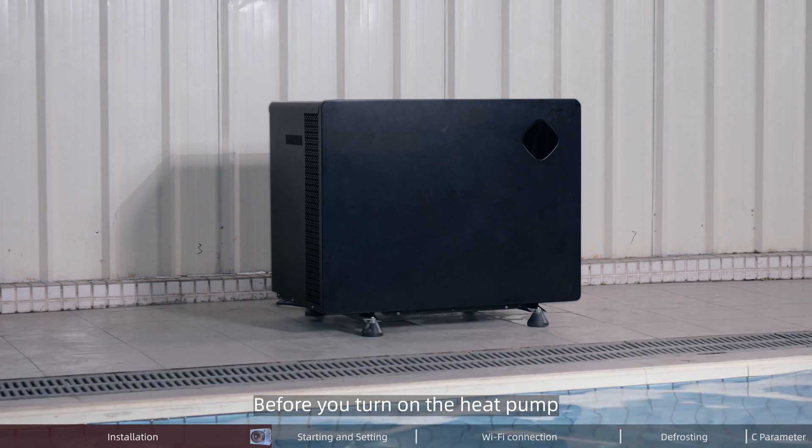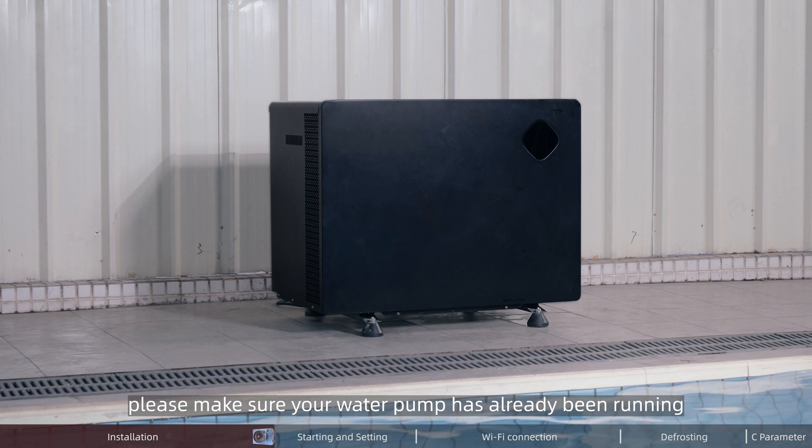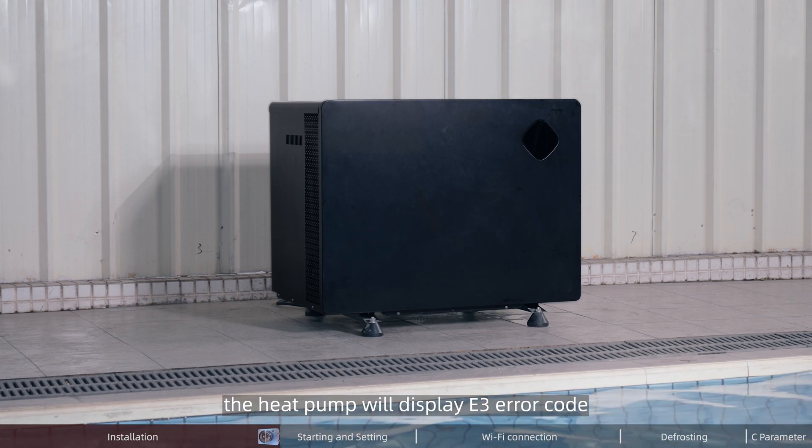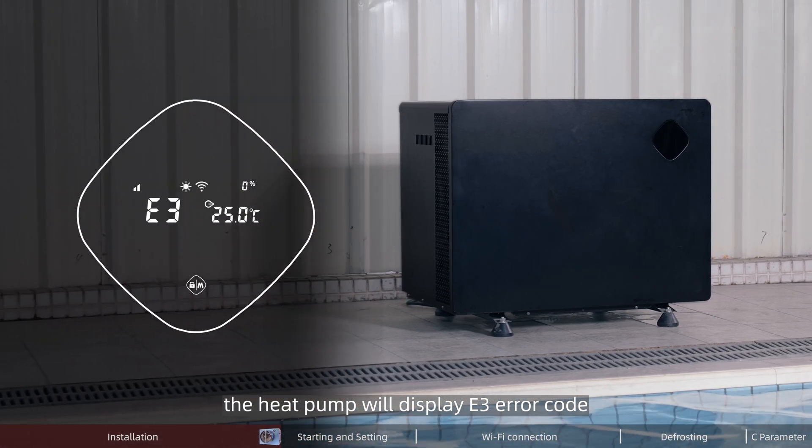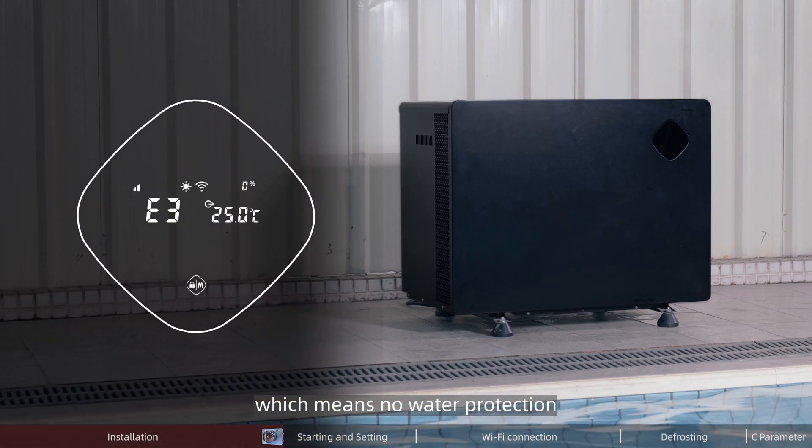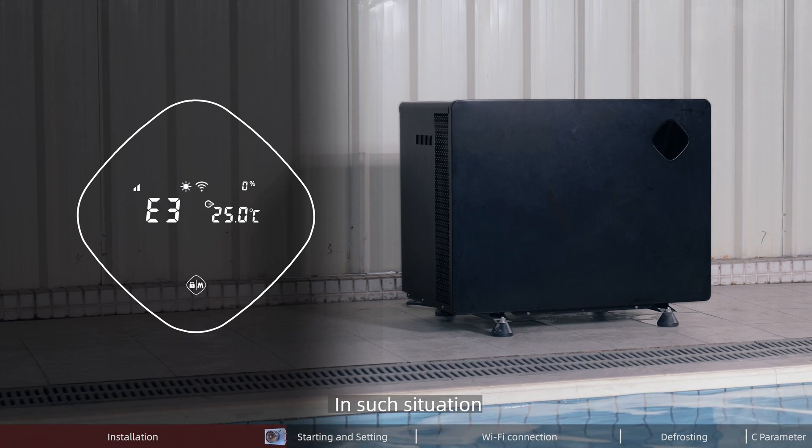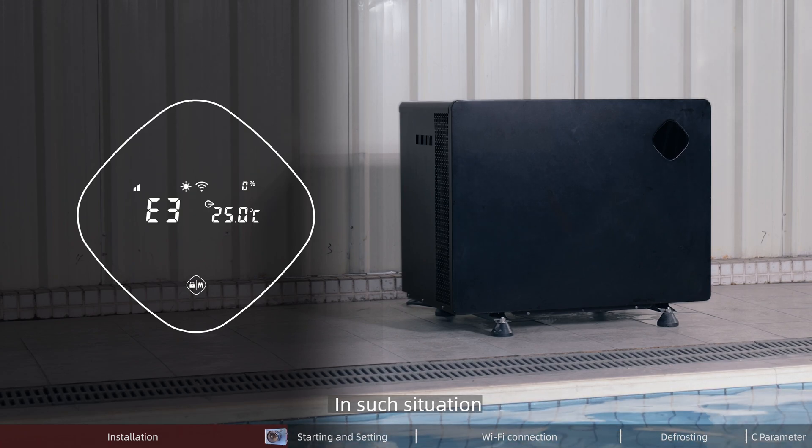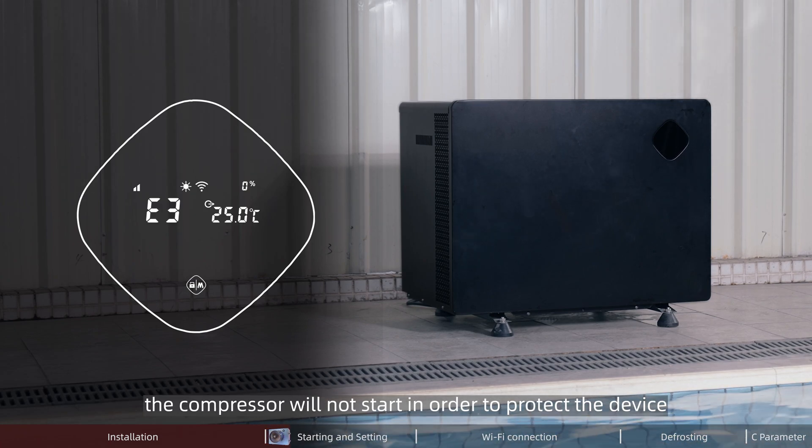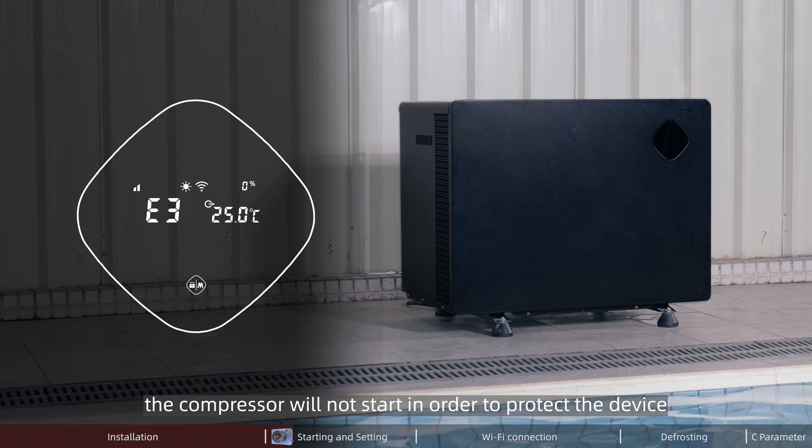Before you turn on the heat pump, please make sure your water pump has already been running. Otherwise, the heat pump will display E3 error code, which means no water protection. In such situation, the compressor will not start in order to protect the device.